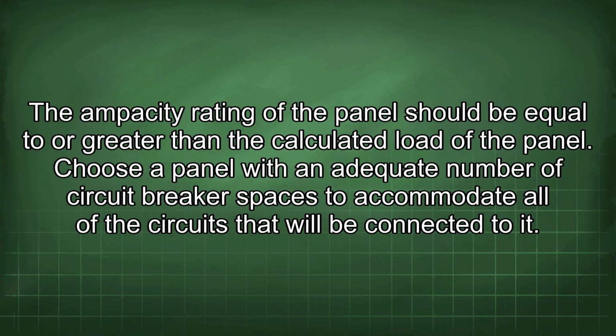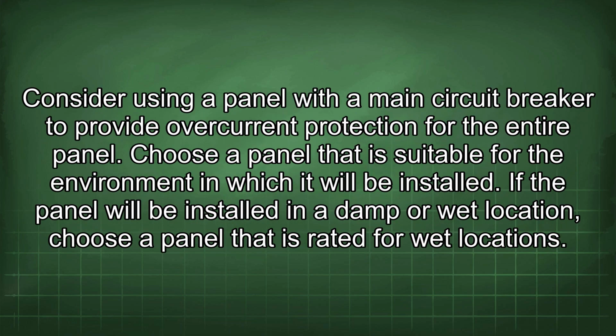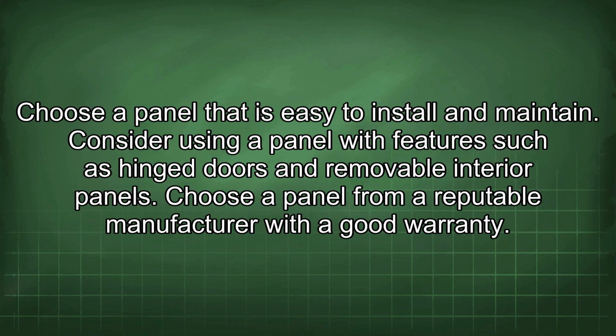Choose a panel with an adequate number of circuit breaker spaces to accommodate all of the circuits that will be connected to it. Consider using a panel with a main circuit breaker to provide overcurrent protection for the entire panel. Choose a panel that is suitable for the environment in which it will be installed. If the panel will be installed in a damp or wet location, choose a panel that is rated for wet locations. Choose a panel that is easy to install and maintain.